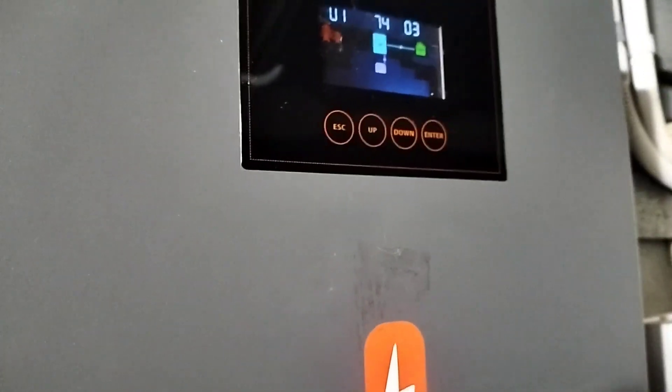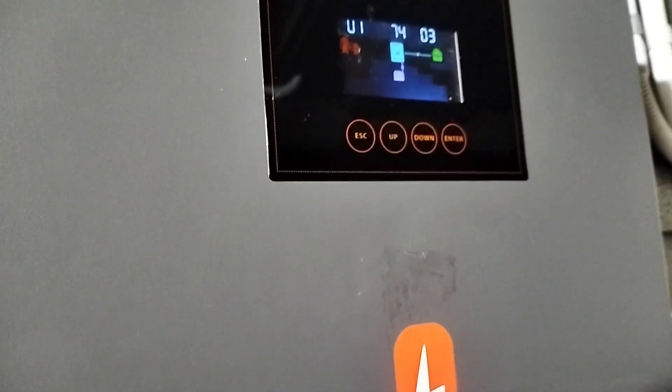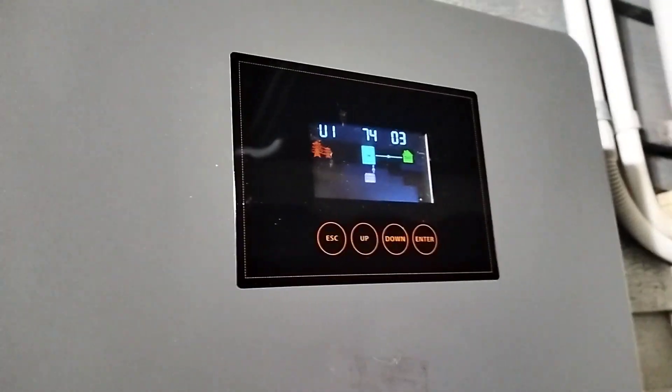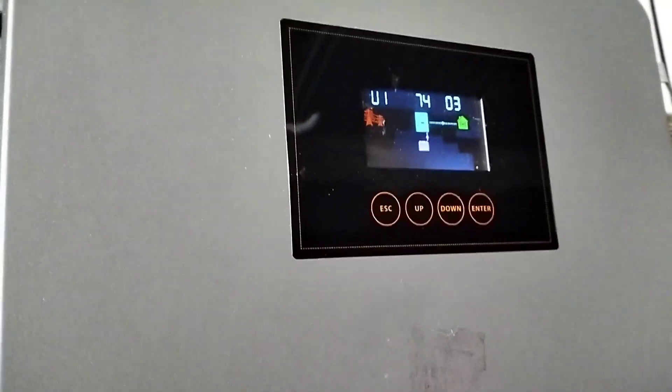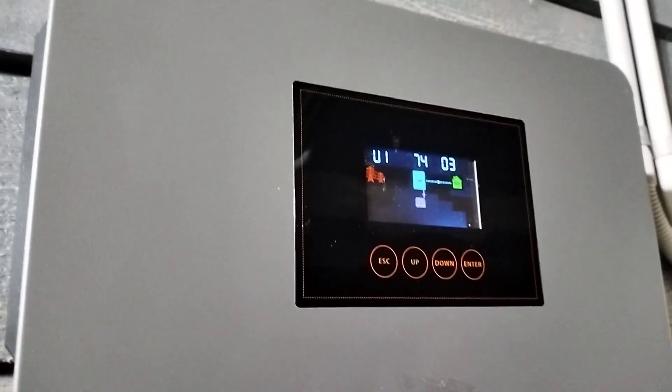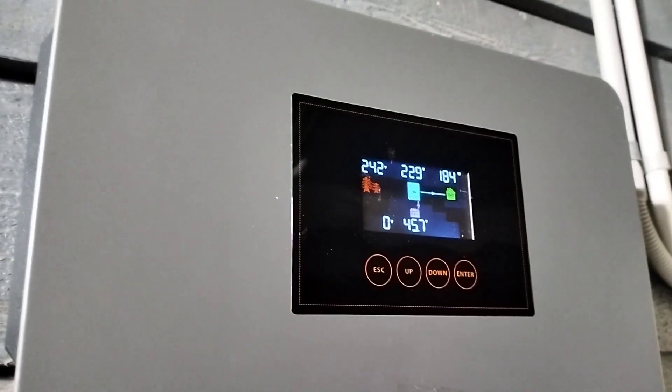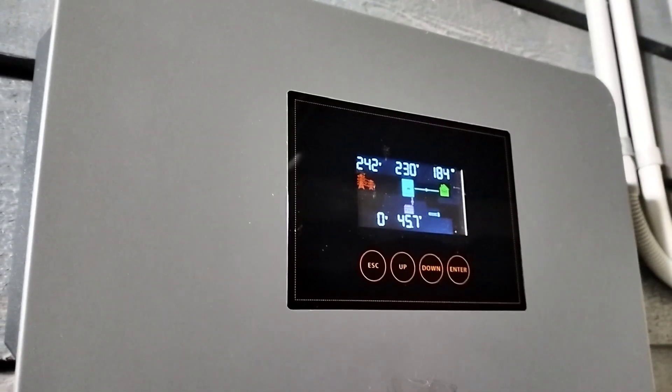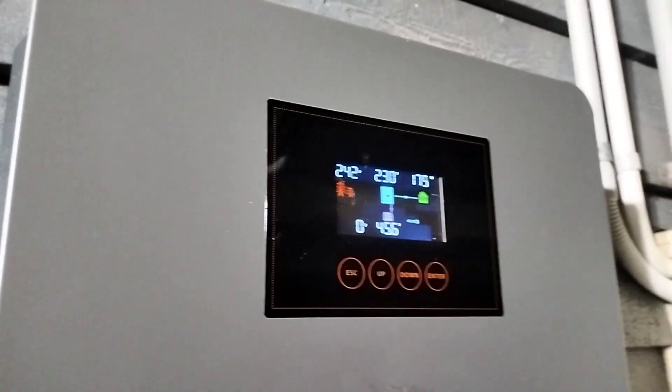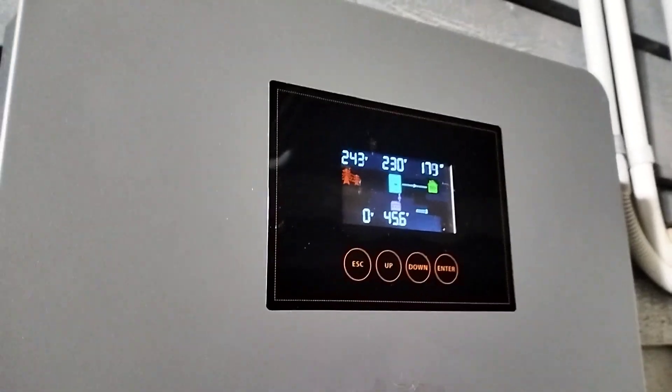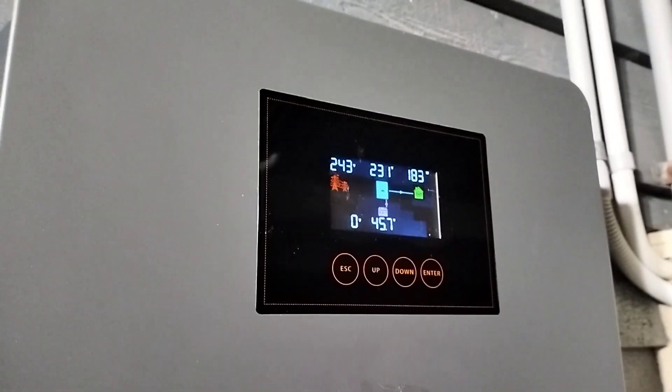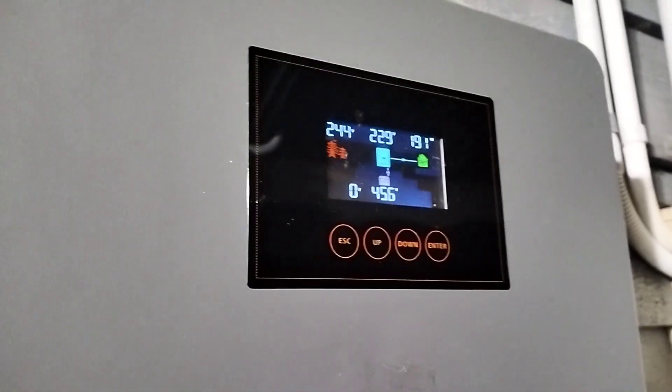The DC isolator, the AC isolator, the inverter output isolator. I want them all in this one cabinet and they'll all be labeled. So there'll be instructions on how to shut it down and how to start it up properly so you don't damage anything. If you improperly shut a DC system down, you will cause damage and it can be catastrophic.